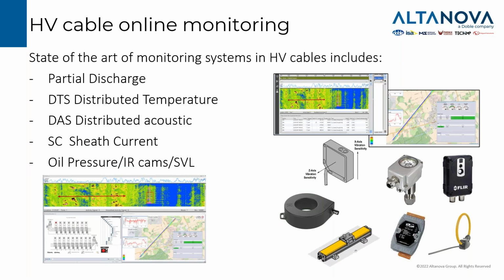So what can we monitor on high voltage cables? We can monitor partial discharge, temperature, acoustic signals, sheath currents, and others. In some specific cases, our monitoring system included, for example, infrared cameras from the manholes, SVL monitoring, or oil pressure deterioration monitoring.